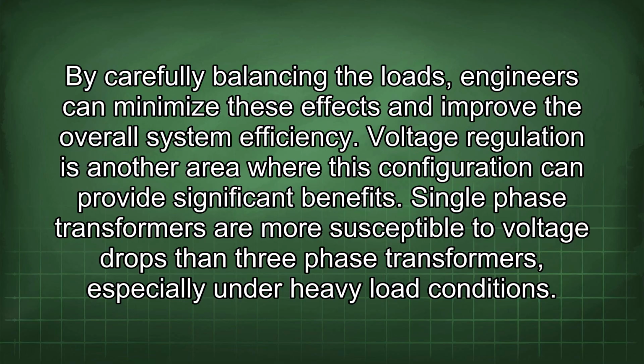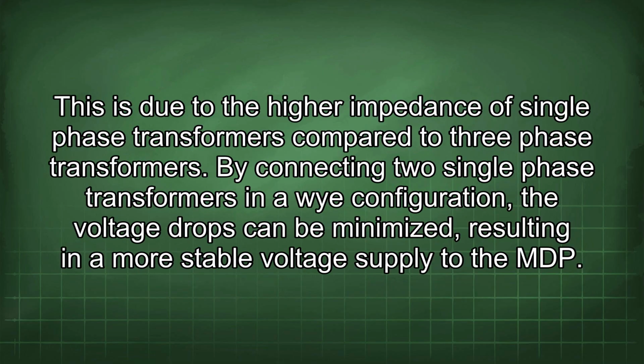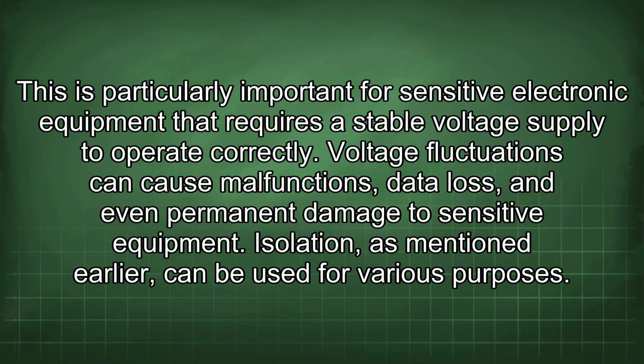Voltage regulation is another area where this configuration can provide significant benefits. Single-phase transformers are more susceptible to voltage drops than three-phase transformers, especially under heavy load conditions. This is due to the higher impedance of single-phase transformers compared to three-phase transformers. By connecting two single-phase transformers in a Y configuration, the voltage drops can be minimized, resulting in a more stable voltage supply to the MDP. This is particularly important for sensitive electronic equipment that requires a stable voltage supply to operate correctly. Voltage fluctuations can cause malfunctions, data loss, and even permanent damage to sensitive equipment.